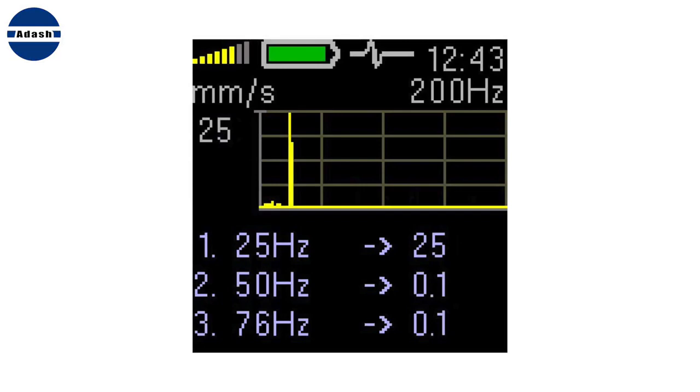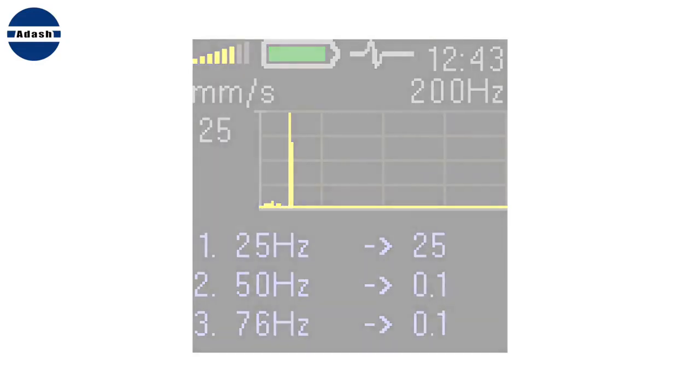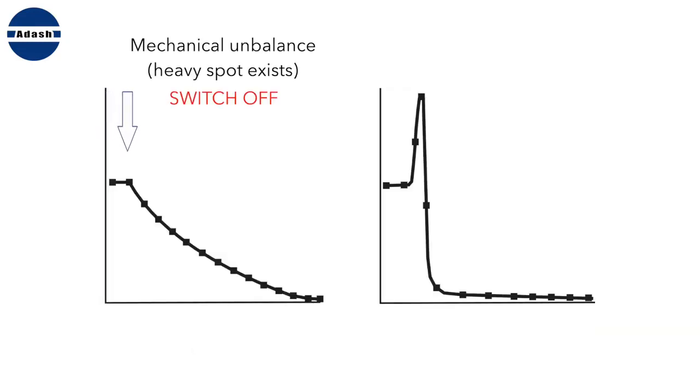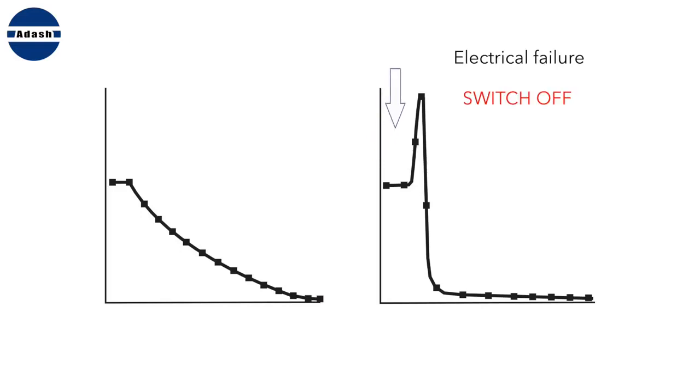The unbalance can be mechanical. Then you will do the balancing job. Or the unbalance can be electrical, of course only for motors. When electrical failure exists, then it also generates only one spectrum line on speed frequency. Fortunately, you can do simple test. Watch the velocity value and switch the motor off. If the velocity value decreases together with speed decreasing, then the mechanical unbalance is the failure. When the velocity promptly drops to almost zero, then it is electrical failure. In this case, the value can increase in the beginning and then drops. It is also normal.